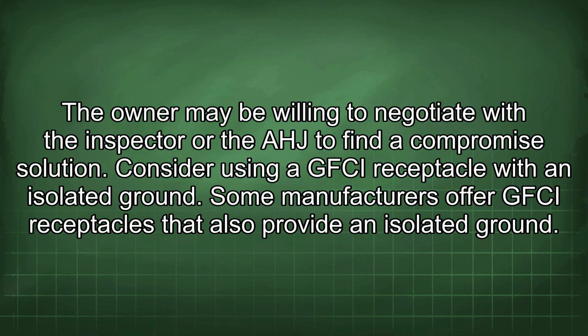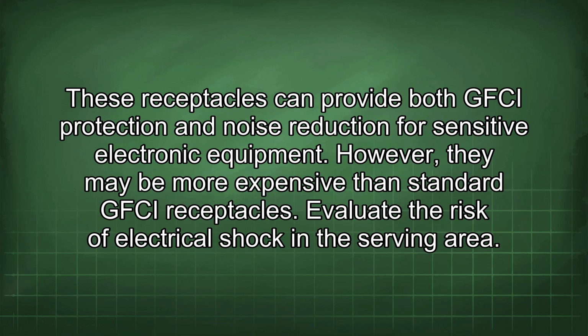Consider using a GFCI receptacle with an isolated ground. Some manufacturers offer GFCI receptacles that also provide an isolated ground. These receptacles can provide both GFCI protection and noise reduction for sensitive electronic equipment. However, they may be more expensive than standard GFCI receptacles.